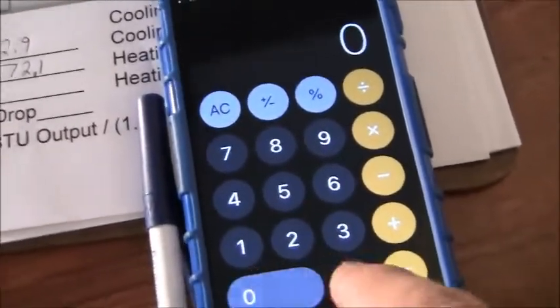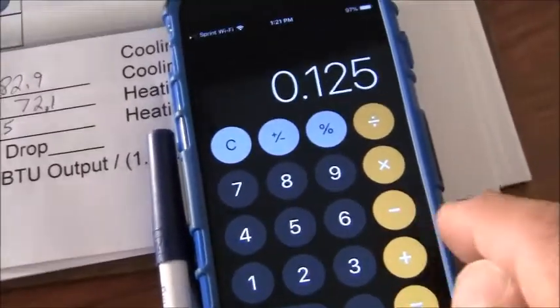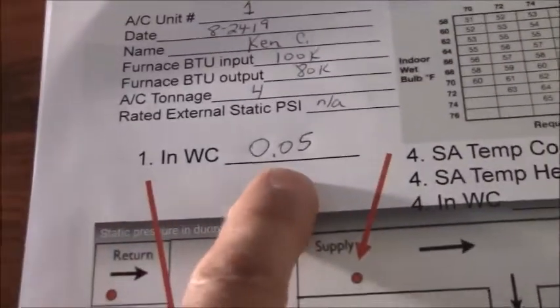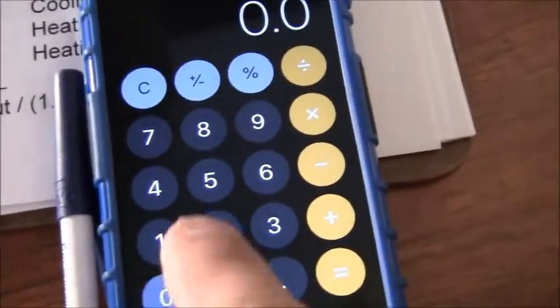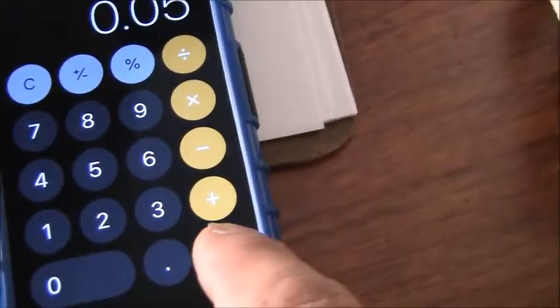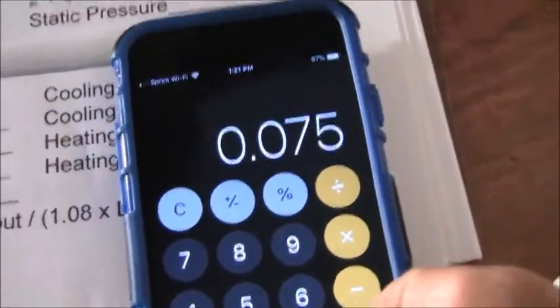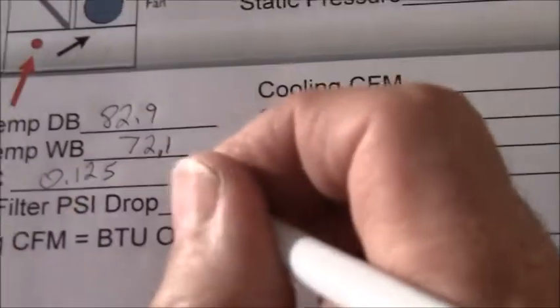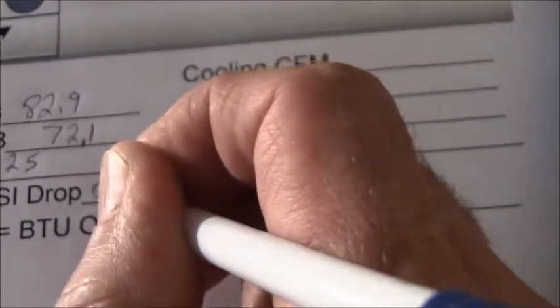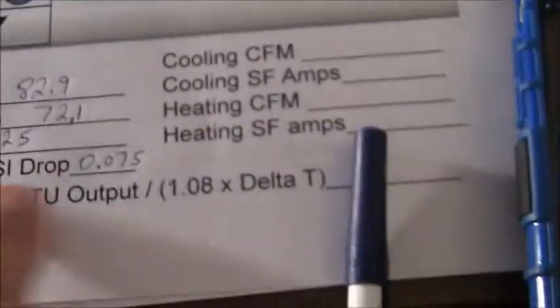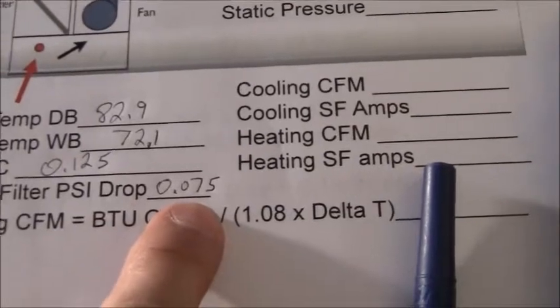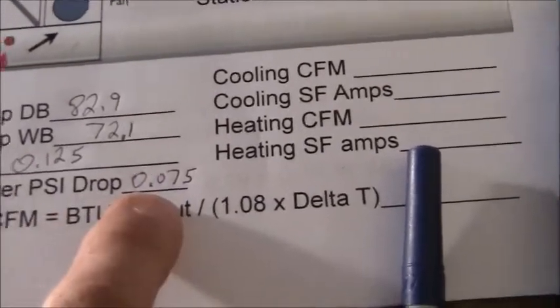0.125 subtract number 1, 0.05, 0.05 equals 0.075. So that is 0.075. Now, that's pretty good. That's not a bad pressure drop across the filter. Mind you, I just cleaned it.